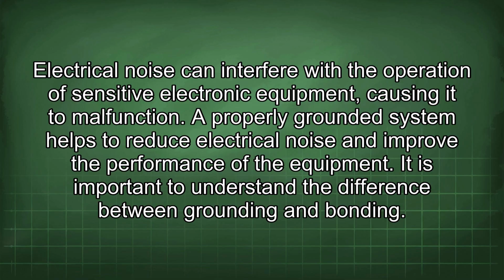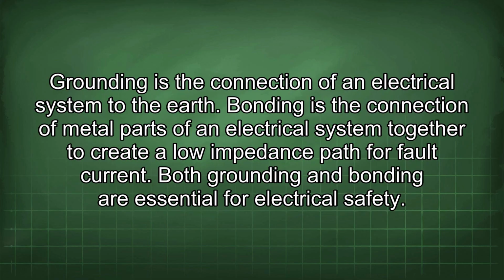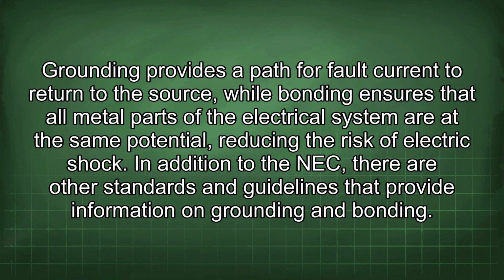It is important to understand the difference between grounding and bonding. Grounding is the connection of an electrical system to the earth. Bonding is the connection of metal parts of an electrical system together to create a low impedance path for fault current. Both grounding and bonding are essential for electrical safety. Grounding provides a path for fault current to return to the source, while bonding ensures that all metal parts of the electrical system are at the same potential, reducing the risk of electric shock.